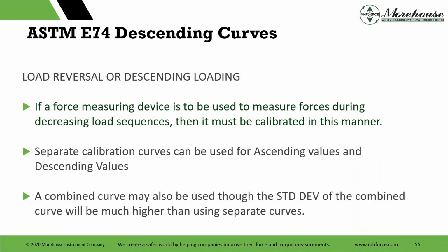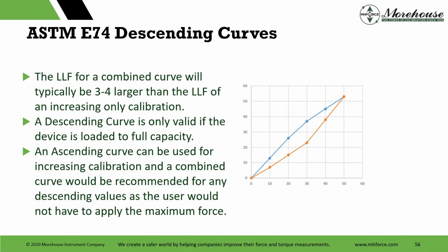What we say is, if a force measuring device is to be used to measure forces during a decreasing load sequence, then it must be calibrated in that manner. Separate calibration curves can be used for ascending values and descending values. A combined curve can also be used, though the standard deviation is going to be higher, meaning your lower limit factor is going to be higher.